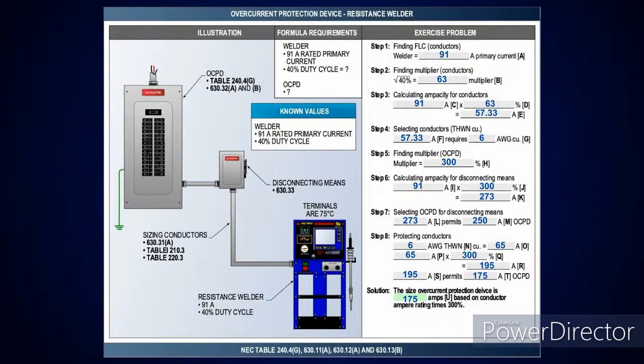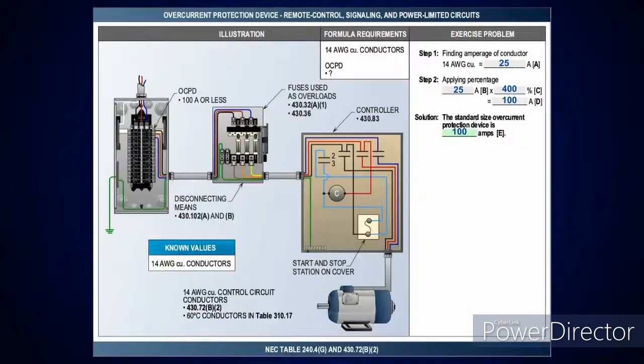So it might be a good idea to learn this calculation, because if they're asking you for the minimum size on the test, guess what? You're going to be looking at 175 amp. Okay? So those are your ways of calculating this for non-motor, motor, and resistance type arc welders.